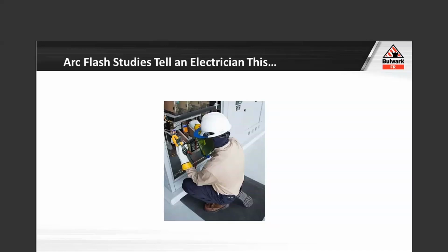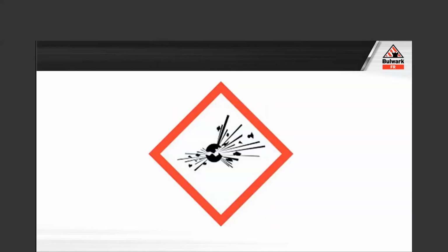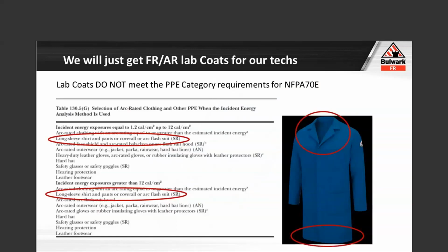Unfortunately, without the arc flash study being done and without the labeling being done, unless I'm educated on 70E and I can utilize the tables, or I utilize the simplified two-step approach as in Annex H, I am not going to know how to dress in front of that so that I'm protected. So we want to tell our electricians how big a bomb they're standing in front of so they can dress accordingly. The other piece is, and I see this more often than I would like, it still permeates through our industrial complexes, we'll just throw on a flame-resistant arc-rated lab coat because it's made of fabrics that actually have an arc rating, and I can just do that temporarily because that'll be my task-based solution. My electricians will get to wear their cotton.